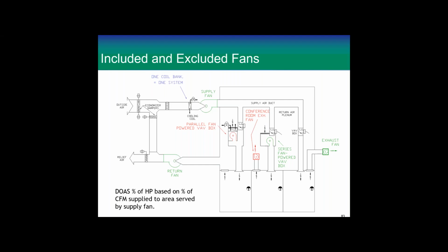about the motor. We have a requirement for only so much energy being used, in motor horsepower per CFM, so that we're limiting the amount of horsepower you can use in your fan systems. The way it works is you'll have a supply fan. The supply fan is the fan that has a coil on it. It's the main fan. You'll have the CFM through the supply fan. This comes down and goes through a VAV box. That doesn't use any energy, that's fine. Then it goes through a series fan powered box. This fan power uses energy at design condition, so you have to add this fan to this fan. That's what we're talking about, horsepower.